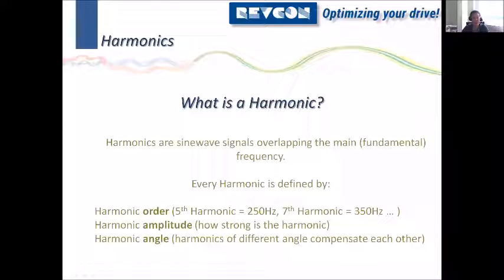To sum up, what is a harmonic? Harmonics are sine wave signals overlapping the main fundamental frequency. And every harmonic is defined by three things. The first one is harmonic order. That's the integer number of the harmonic. So the fifth harmonic is 250 hertz. I'm always speaking about 50 hertz, by the way, unless called otherwise.